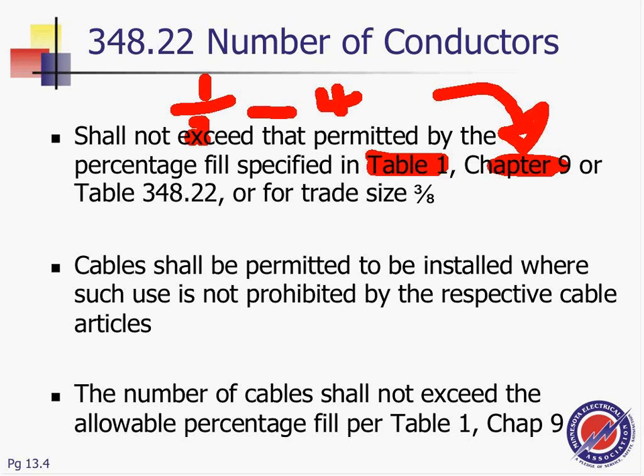For that special little conduit size, only for this size, they have a special table for you. And my friend, in a journeyman exam, look out. In a journeyman exam, they have a question about how to use it, and they require you to go directly to Table 348.22. They give you a 3/8 inch flexible metal conduit and ask how many conductors you can fit in a 3/4 inch flexible metal conduit.